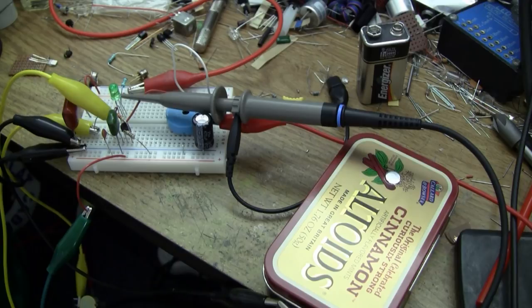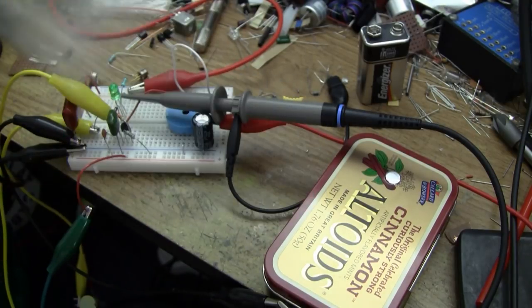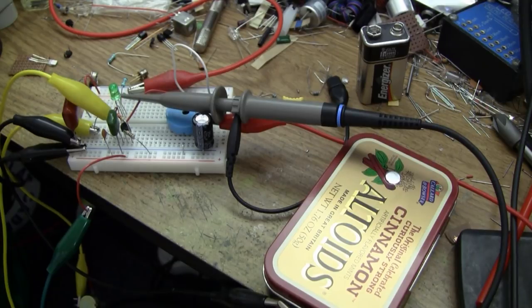It seems to have an energy level, minimum level, of about 50-60 keV. It can only just detect the signal from an americium source. If I put the americium source right up against it inside the box, the aluminium foil is actually too much. Also, I tried it with an X-ray beam at very low energies and had similar problems.